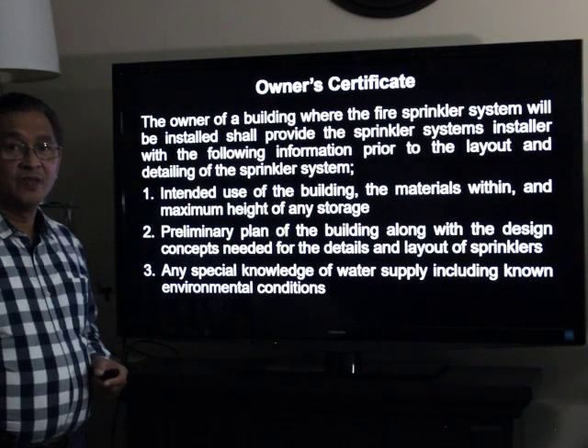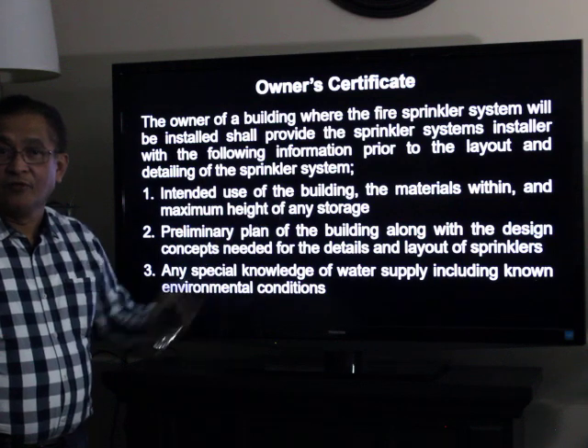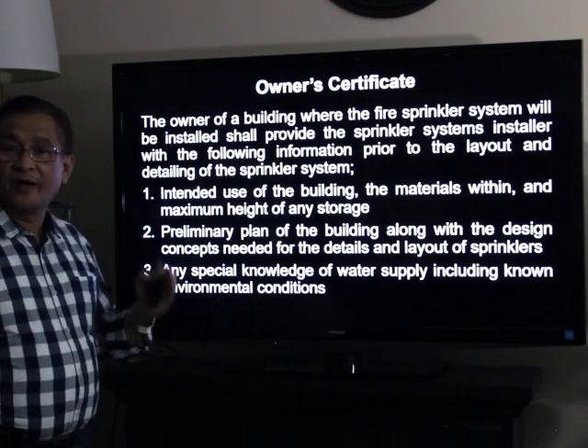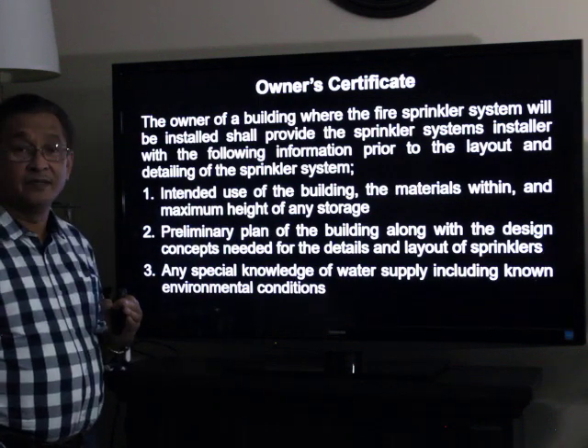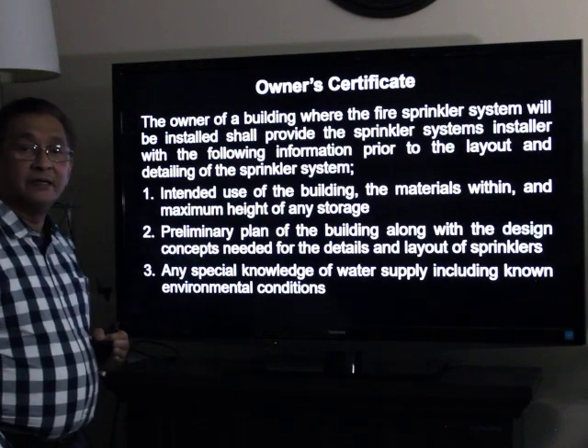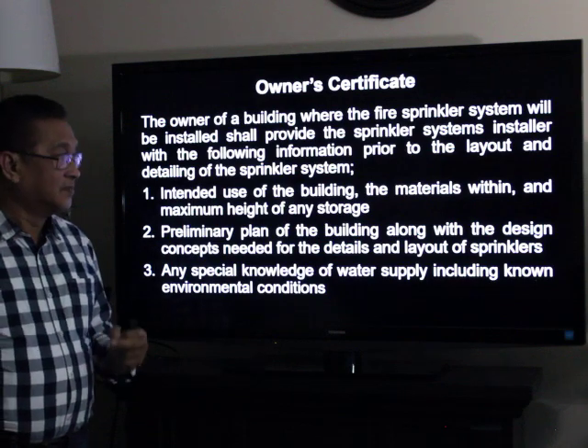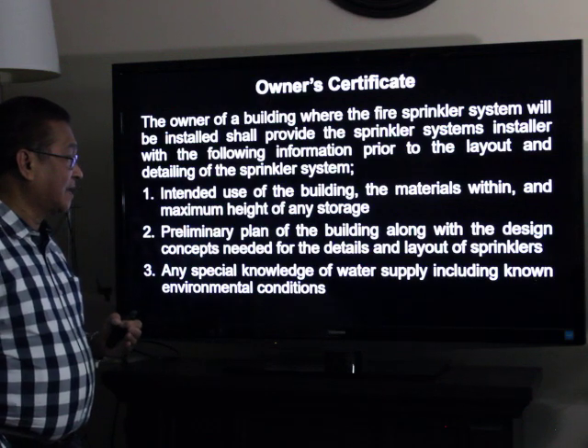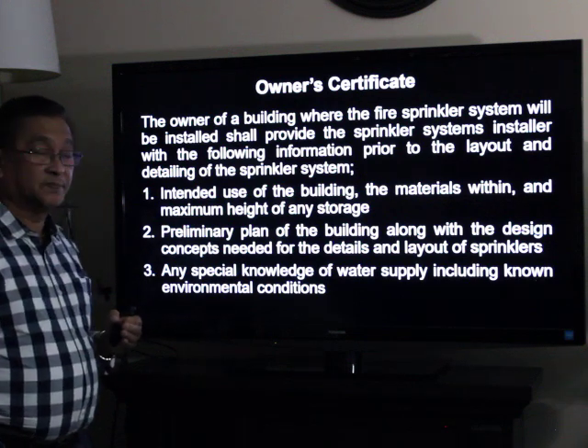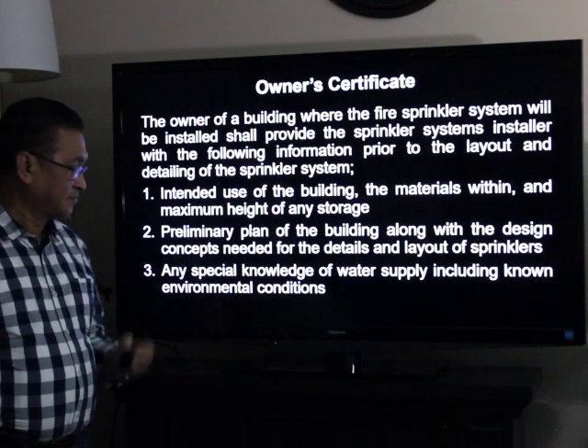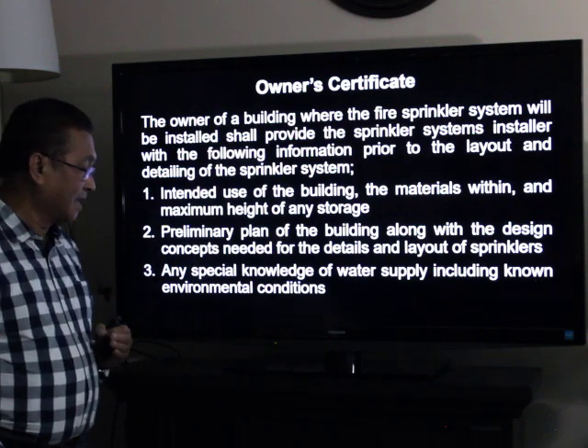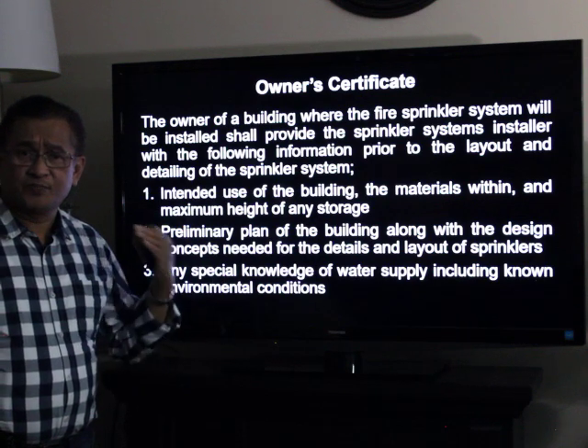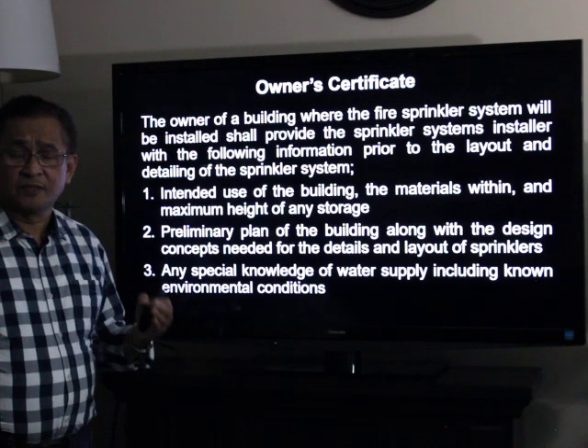Owner's certificate: before the design is started, the owner's certificate is always needed. The owner of the building where the fire sprinkler system will be installed shall provide the sprinkler system installer with the following information: number one, the intended use of the building, the materials within, and the maximum height of any storage; second, the preliminary plan of the building along with the design concepts; and third, any special knowledge of water supply including environmental conditions, such as exposure to corrosion or other special conditions.